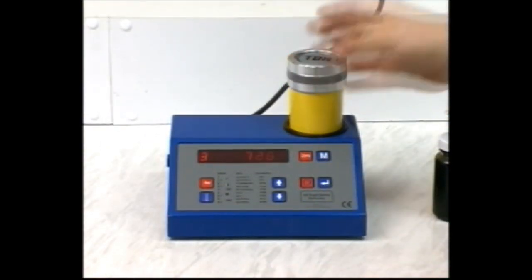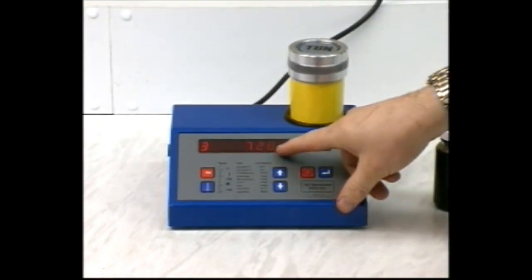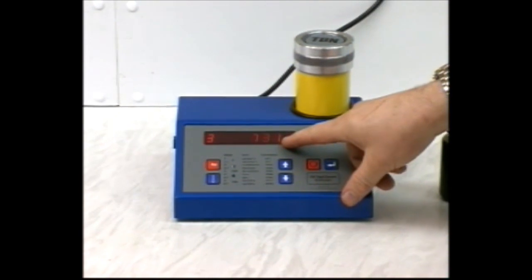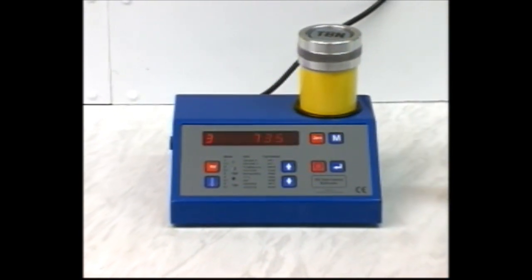To test for TBN depletion in used oil, repeat the procedure just outlined, replacing the new oil with an equal amount of used oil. The figure displayed on the unit at the end of the procedure is the test value. This will be used for calculating TBN depletion.